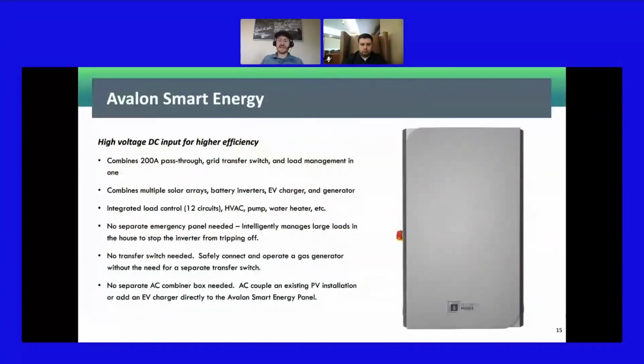Moving on to the next component, we have the Avalon Smart Energy Panel. This is really the brains of the entire system and what helps differentiate the Avalon system from a lot of the other products on the market. The Smart Energy Panel has a 200 amp pass-through, a grid transfer switch, and load management all within one panel. It can combine multiple solar arrays and batteries, inverters, EV chargers, generators, whatever it is that you need to add to the system.